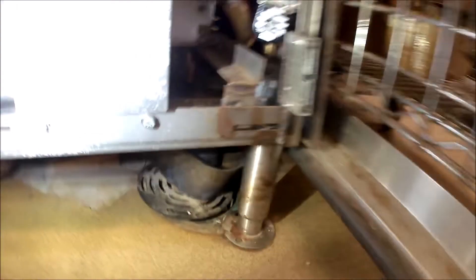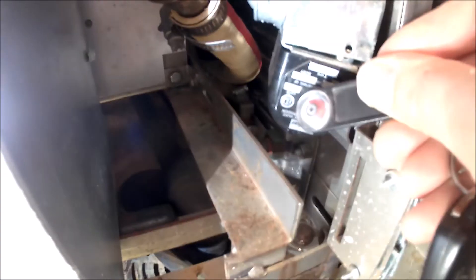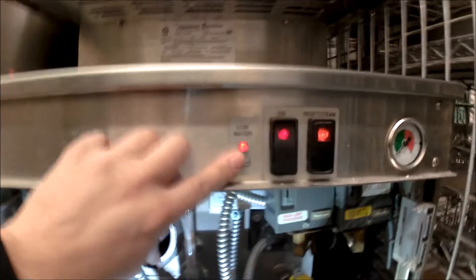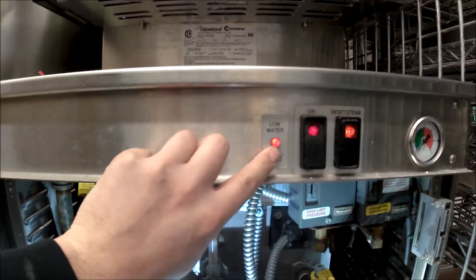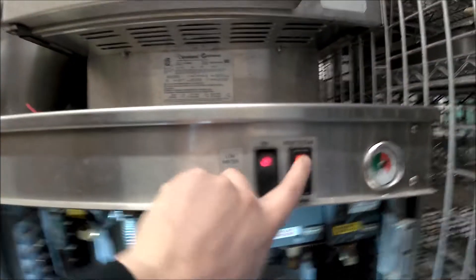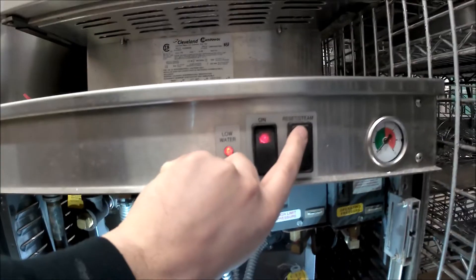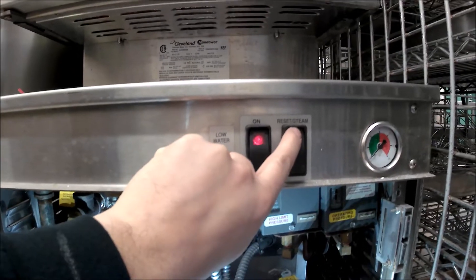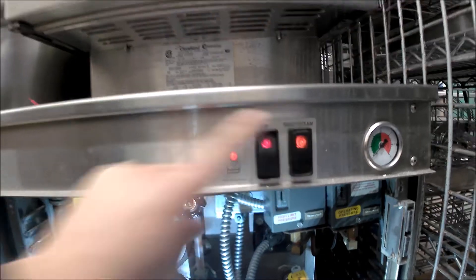The filling has completed, there's no more power to the solenoid, but we still have our low water light on, which means we cannot turn on our burner. It's not going to allow us.